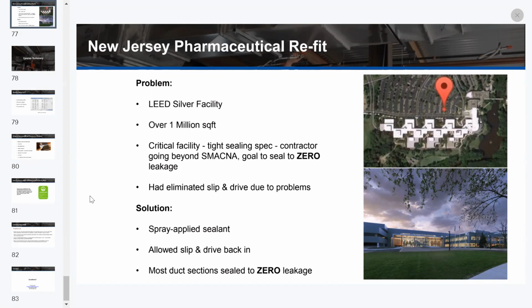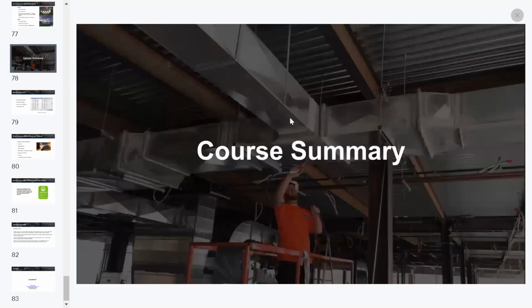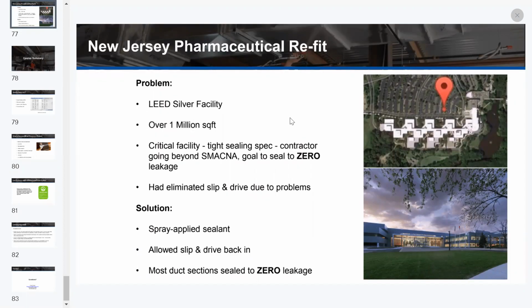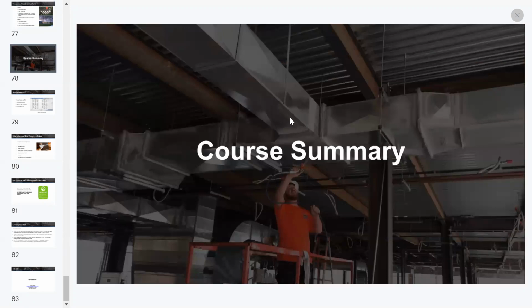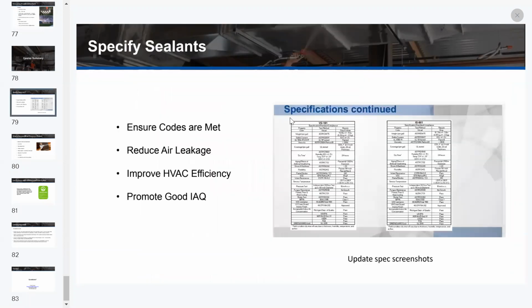The ease of use and sealing capabilities with the spray pump allowed the slip and drive construction to come back in on this job. It was low pressure ductwork. So that was a large cost savings just from the duct construction style. And then when testing for leakage, they only required 1 test, and they were able to meet their criteria. And interestingly enough, on that particular job, most of the sections of duct system that they sealed actually had 0 leakage.